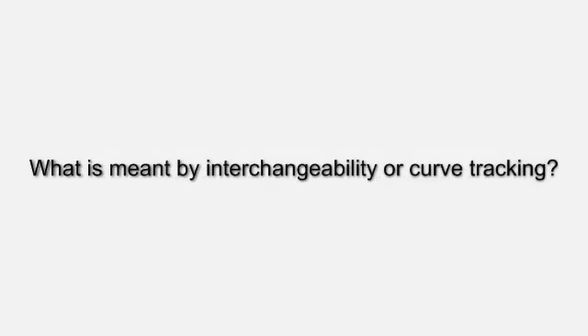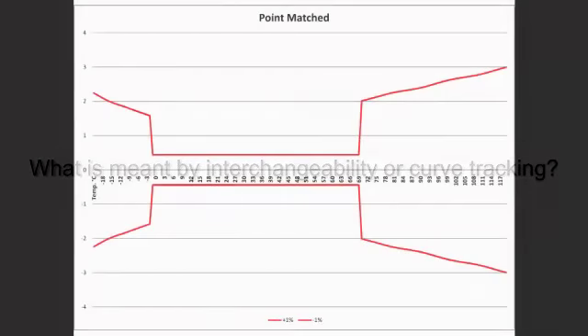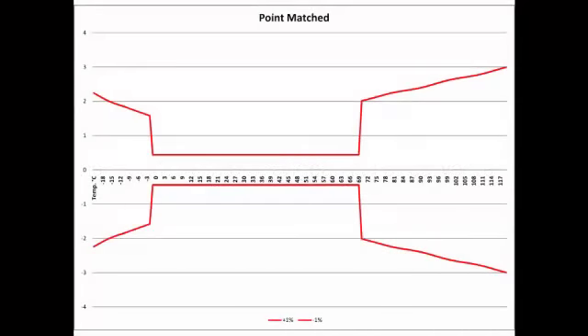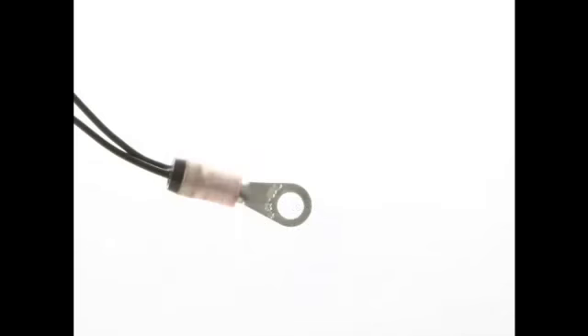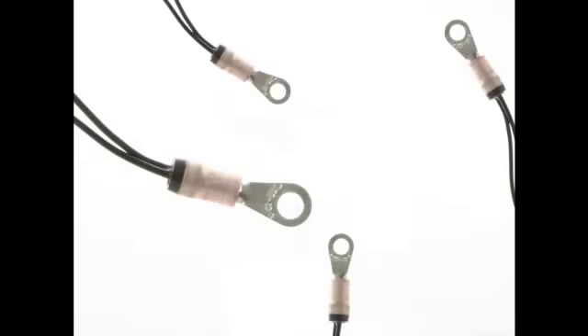A thermistor can be defined as having an interchangeable tolerance of plus or minus 0.1 degrees C over the range from 0 to 70 degrees C. This means that all points between 0 to 70 degrees C are within 0.1 degrees C of the nominal resistance values for that particular thermistor curve. This feature results in temperature measurements accurate to plus or minus 0.1 degrees C, no matter how many different thermistors are substituted in the application.